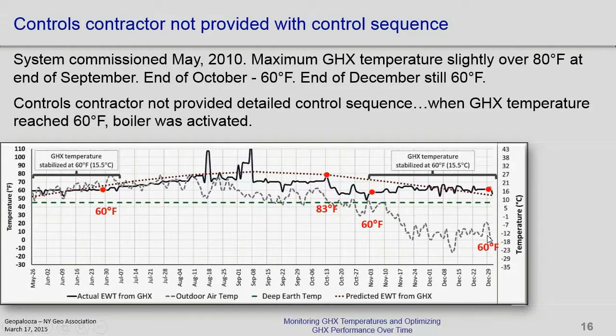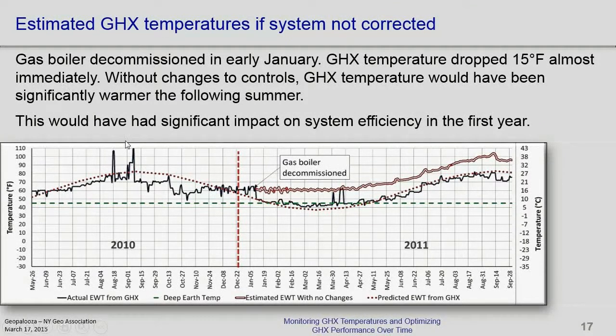So what happened then was basically the gas boiler was decommissioned. Temperature dropped virtually immediately. Here's what the temperature should have been, and it got pretty close to there. If this hadn't been caught, this wasn't the problem here. It probably wouldn't have been a problem till probably around here, the end of August, if maybe not the first year, but certainly the second year. Temperature would have gone up higher than it should have been. It probably would have been running at about 60 degrees, and then at this point here in the beginning of summer, there was enough heat coming from the building air conditioning that the boiler wouldn't come on, but the temperature would stay up there.